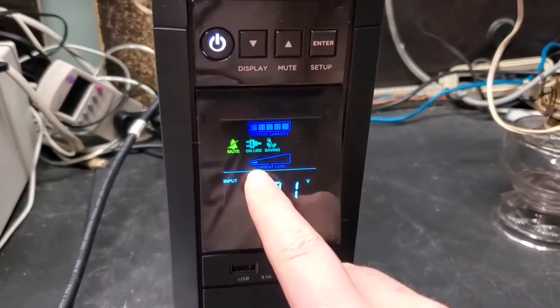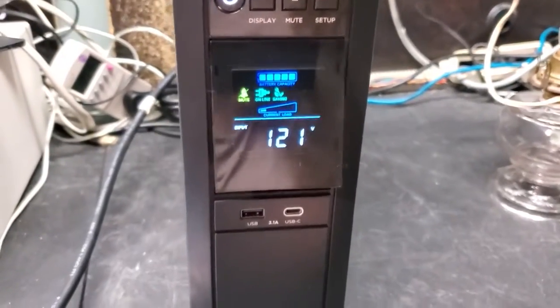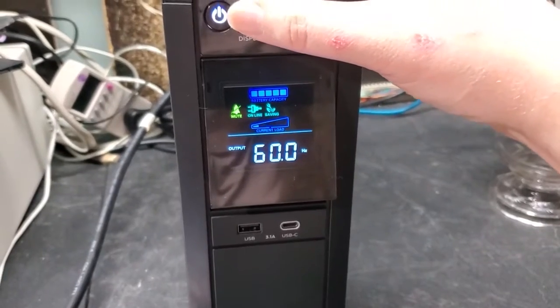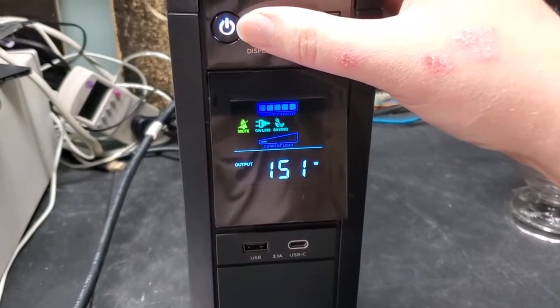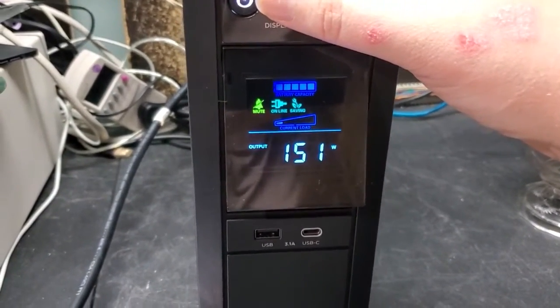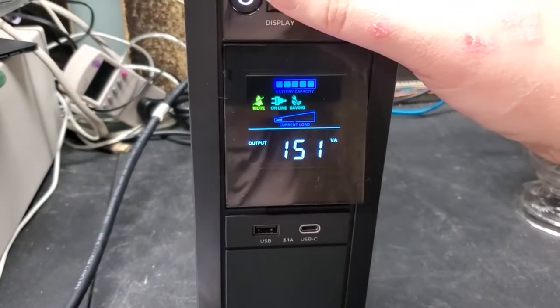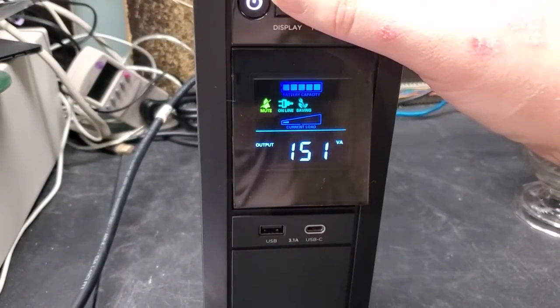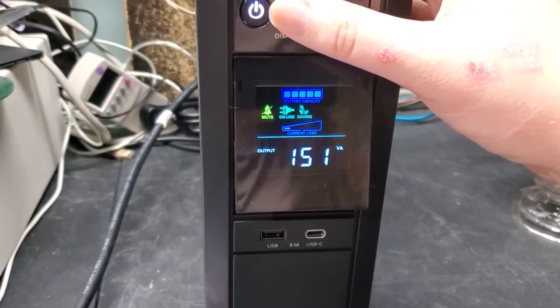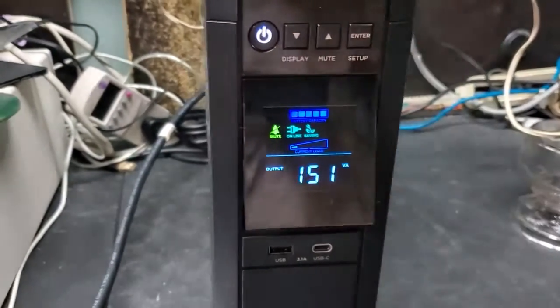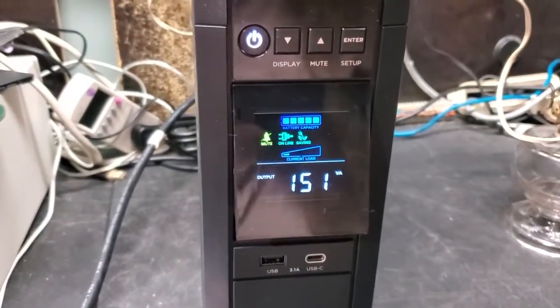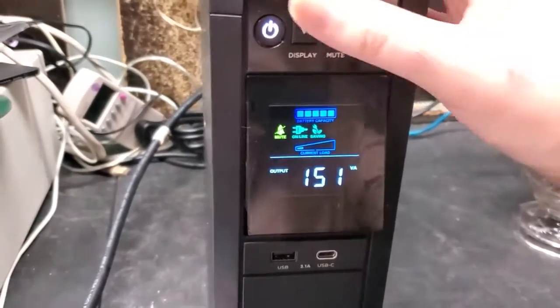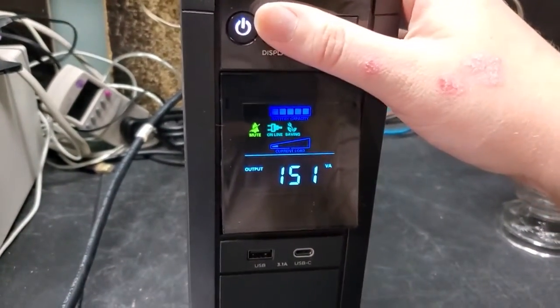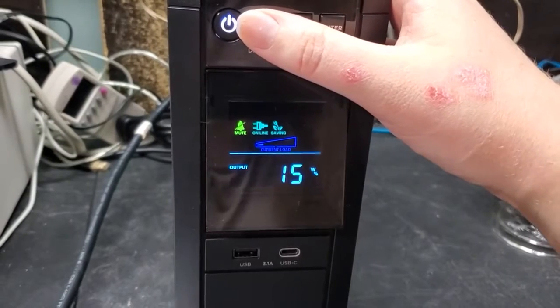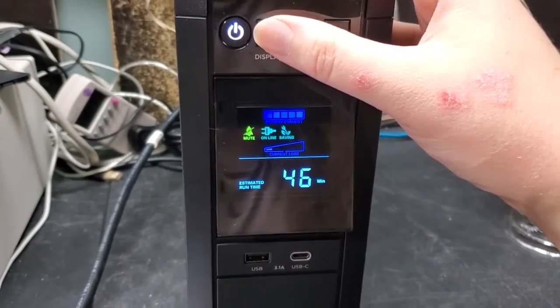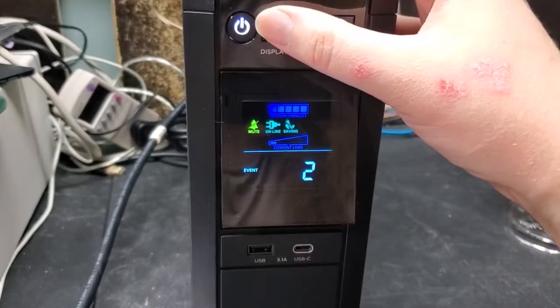You can see we're on the first bar of the current load, and if we look at the watt output, 151 watts, so that's pretty accurate. It's also reading 151 volt amps. That's not accurate, it should be reading 10 or 20 volt amps more because of the fluorescent light. Interesting, maybe it's just not enough of a difference to matter. And it has an estimated runtime of 46 minutes.